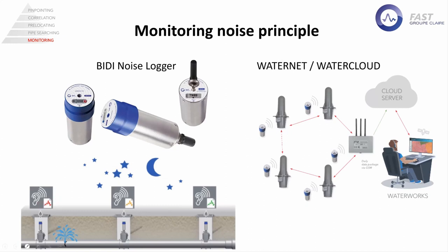What happens if a leak is close by, as shown in this small illustration? The logger will record louder noise than the loggers further away from the leak. This minimum noise will then be increasing, and every day, as long as you have the same pressure inside the system, you can see the leak sound increasing, so you will know quite specifically that the leak is really growing.